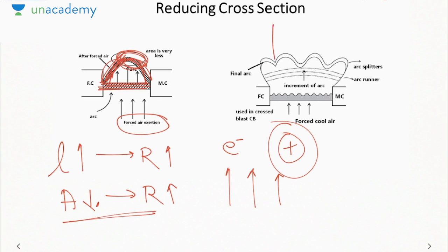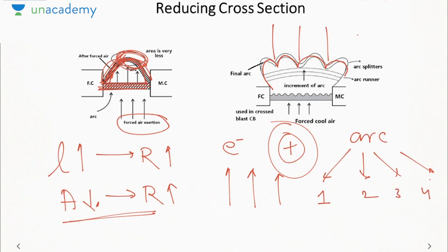Otherwise what we do is keep arc splitters like this, due to which when the arc is formed, it will be split into multiple arcs. Why do we use arc splitters? Because if we reduce the arc into smaller multiple arcs, 1, 2, 3, 4, these arcs are easier to extinguish since they are smaller and less severe. That is why we make use of arc splitters, due to which the arc becomes less dangerous. Also, due to the arc splitter, the effective length increases, due to which resistance, which is directly proportional to length, also increases.